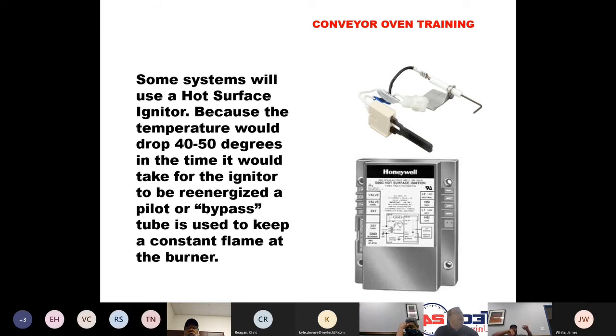Because Lincoln is using hot surface igniters on some other ovens, they have to have that pilot there so that every time the main gas valve is energized, the burner can light instantly. Without that pilot light, they would have to go through the 30 or 40-second process of re-energizing the hot surface igniter, and this would cause a temperature drop in the oven of like 40 or 50 degrees.